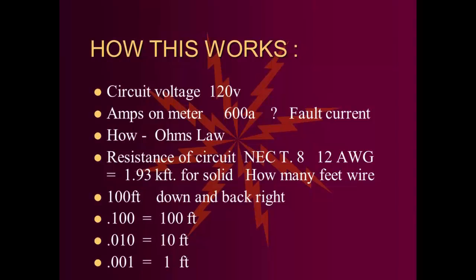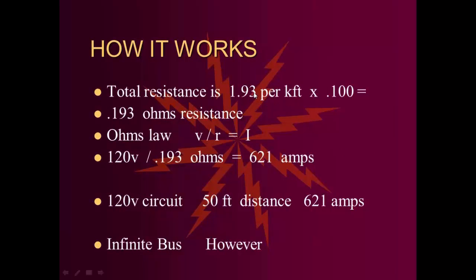And here's how we arrive at that. If you go to the resistance of the circuit, the number 12-gauge wire, in the National Electrical Code, Table 8, 12-gauge wire has a resistance per 1,000 feet of 1.93 ohms, for solid. We have 100 feet of wire, correct? Now, because the table is in 1,000 feet, I'm going to show you a little trick here. If you want to know what 100 feet is, put the decimal point here, 0.100. For 10 feet, it's 0.010. For 1 foot, it's 0.001. Okay? Here's why we're doing this. The total resistance then would be 1.93 per 1,000 feet times 100 feet to get our total resistance. So 1.93 times 0.1 gives you 0.193 ohms resistance.